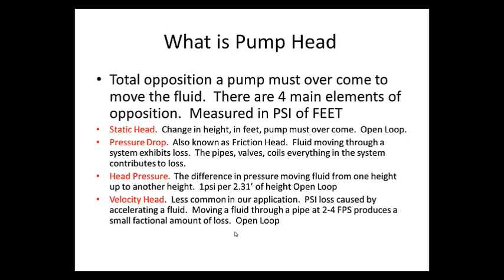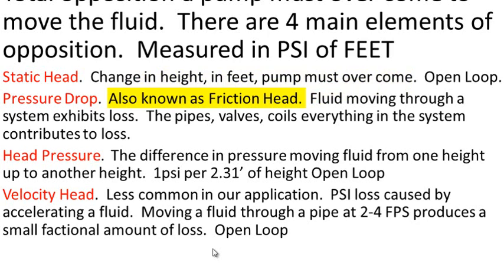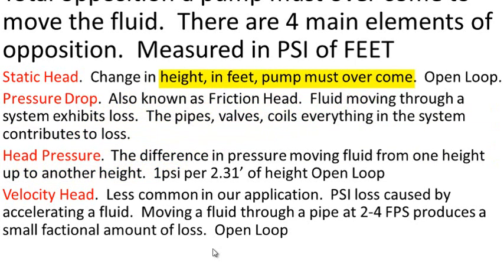When we measure pumps, we always determine pump head, and the pump head is going to tell us how many feet of lift that pump can do. There are four main criteria: static, pressure drop, head pressure, and velocity head. Static head is simply the height that the pump has to overcome. Pressure drop is also known as friction head — these are the lossy losses in the system that you have to account for: valves, pipes, connectors, heat exchangers, the whole bit. Head pressure is the difference required to move that fluid from one height to the other — similar but not quite the same as static head. Static head is the pressure it must overcome from a standing column of water, while head pressure is the force we have to overcome to move that fluid from one height to the other.